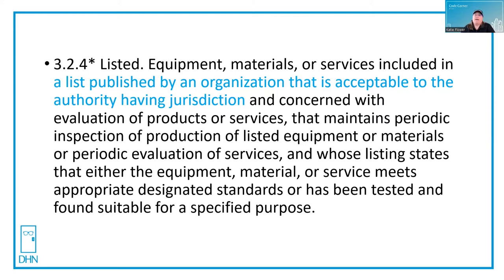Keep in mind that some organizations involved in this type of testing and listing could even be ANSI BHMA and their certified product directory. But if we're talking strictly about listed products for use on fire doors, you would want to make sure that the listing includes UL10C, which is the test for positive pressure swinging fire doors.